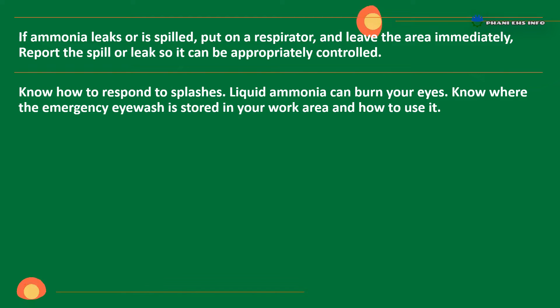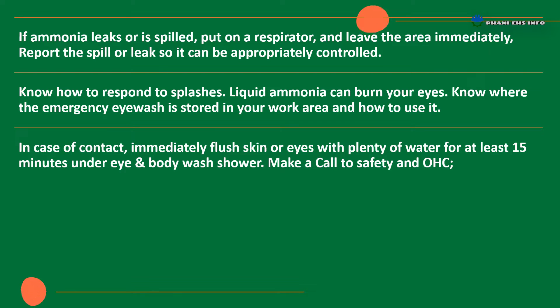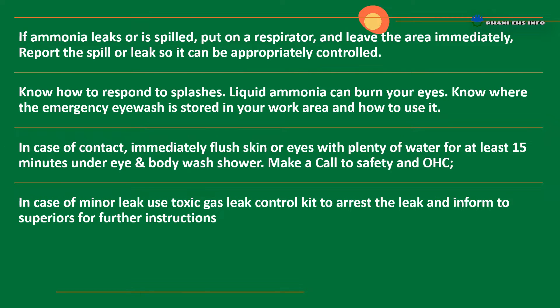Know how to respond to splashes — liquid ammonia can burn your eyes. Know where the emergency eye wash is stored in your work area and how to use it. In case of contact, immediately flush skin or eyes with plenty of water for at least 15 minutes under eye and body wash shower. Make a call to safety and OHC. In case of minor leak, use a toxic gas leak control kit to arrest the leak and inform superiors for further instructions.